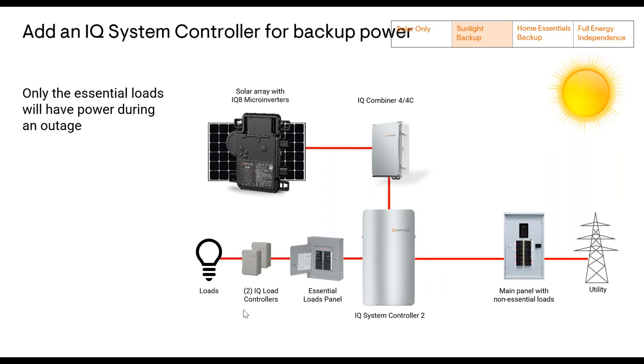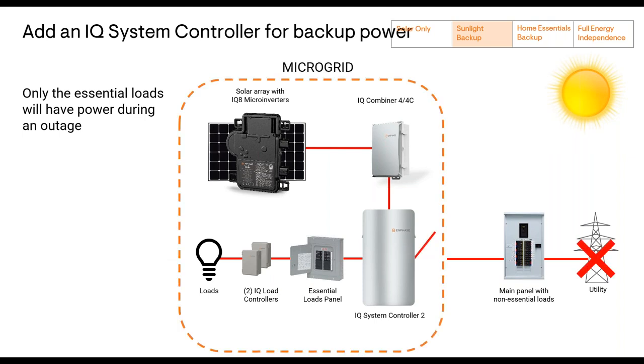And the critical loads that you want to back up during that grid outage will be wired into an essential loads panel, also connected to the system controller. That way, during a grid outage, the system controller has a relay that's gonna open up, and you're able to form a microgrid where your PV is able to supply power to these critical loads.